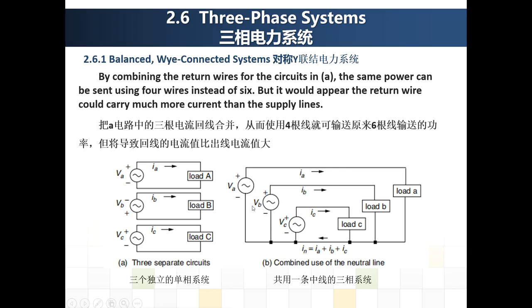However, if VA, VB, VC are in the same phase, the neutral wire, the common return wire, will equal IA plus IB plus IC. When VA, VB, VC are in the same phase, this wire could carry more current than the supply wires.